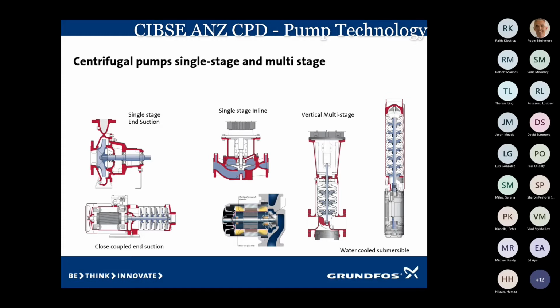The one on the right is a water-cooled submersible pump, and that is what we see sitting in the bore, and that could be 300-400 meters in the ground. The bottom part of the pump is the motor, and that really relies on water passing across the motor into the intake. There's a screen just above the motor, and the water goes through the screen into the first impeller, and then it moves on up the impellers to the discharge. At the top of the pump, there's a non-return.